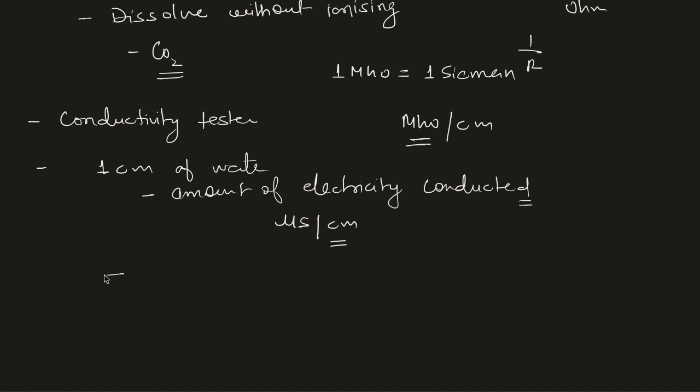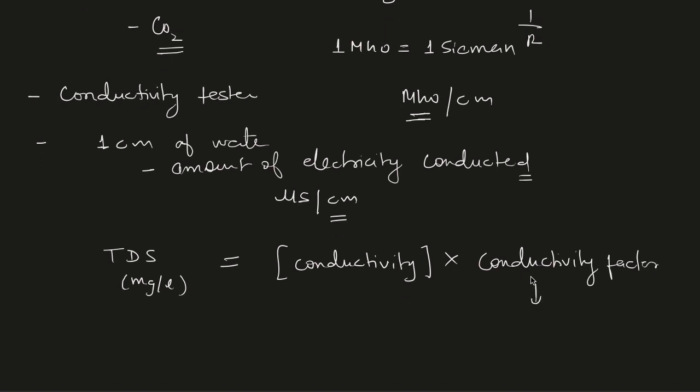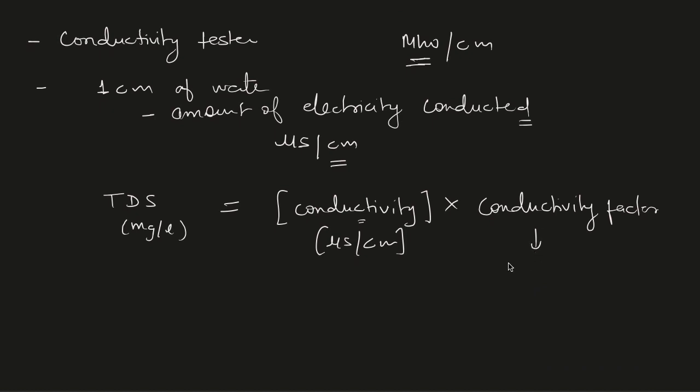If we talk about the relation between TDS and conductivity, there is this standard relation that is TDS in ppm or milligram per liter, it is given as conductivity times the conductivity factor. And the value of this conductivity factor, so this conductivity factor is just a conversion factor, that is converting the conductivity that is in micro siemens per centimeter or micro mho per centimeter into the TDS. So the value of this conductivity factor, it varies between 0.54 to 0.96. And if no other value is mentioned, then an average value of 0.67 can be used for the calculation.